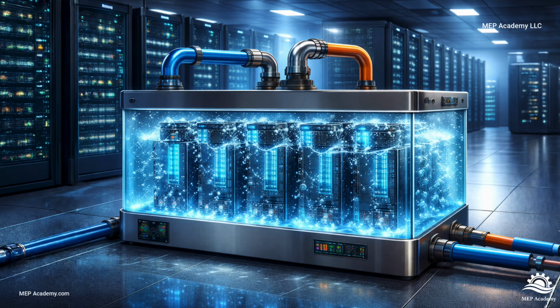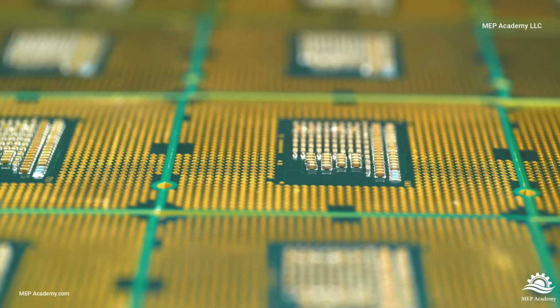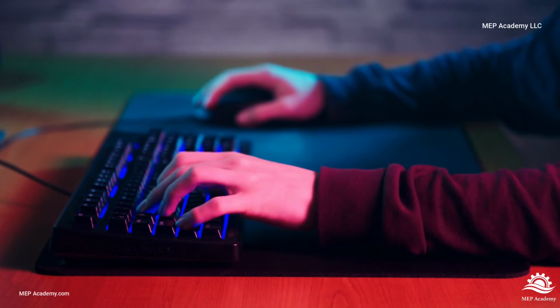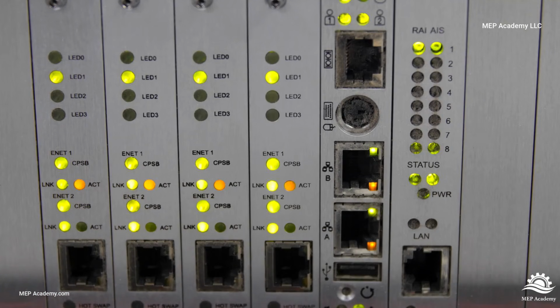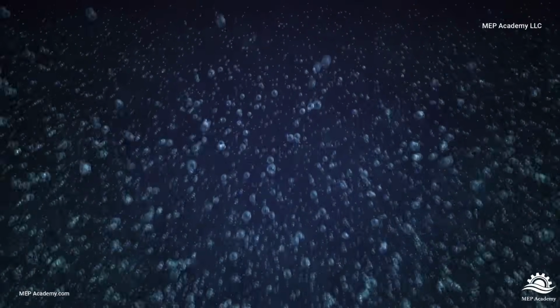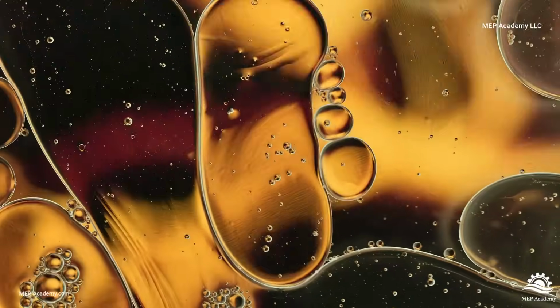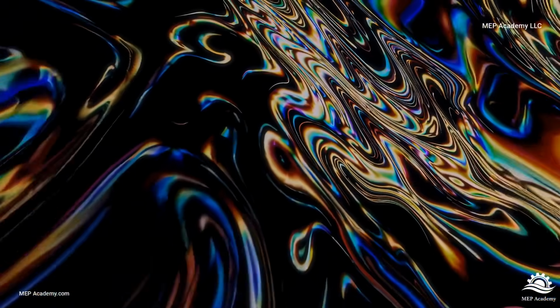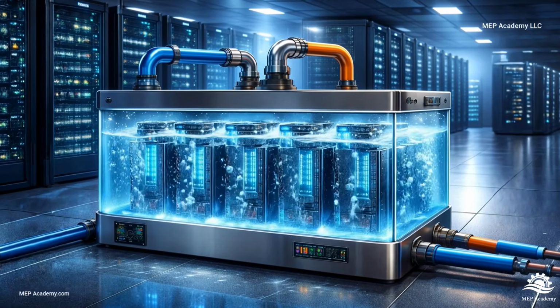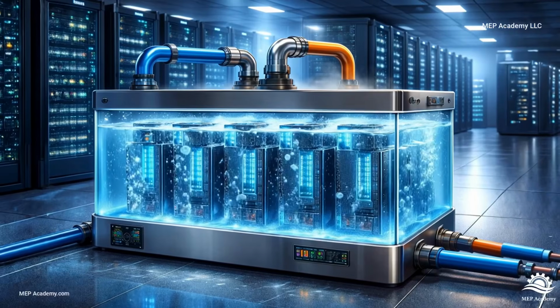Immersion cooling. Now let's talk about the most extreme form of liquid cooling, immersion cooling. Instead of bringing liquid to the server, immersion cooling places the server directly into the liquid. The servers are submerged inside tanks filled with specially engineered dielectric fluids. These fluids do not conduct electricity. That means electronic components can operate safely while completely immersed.